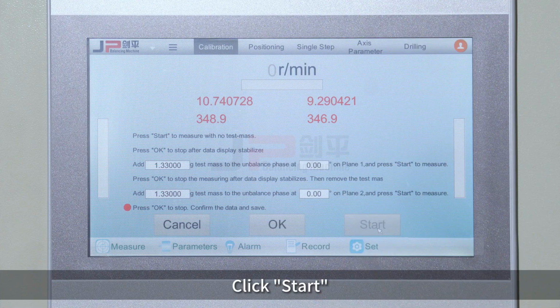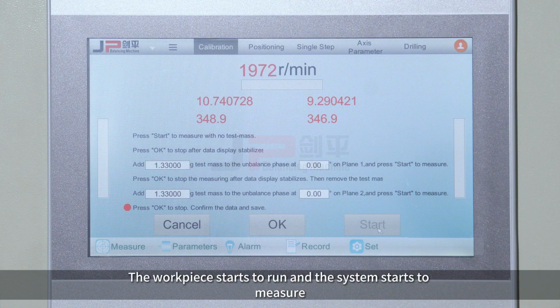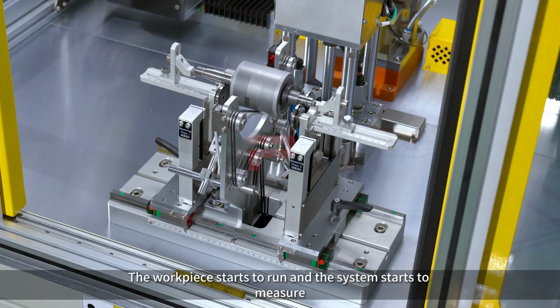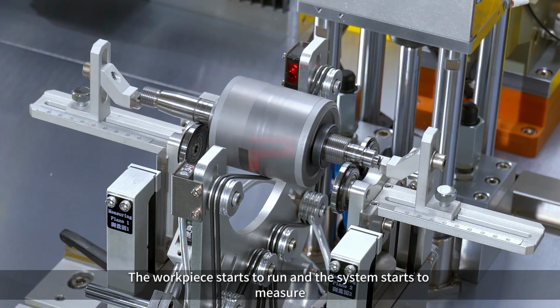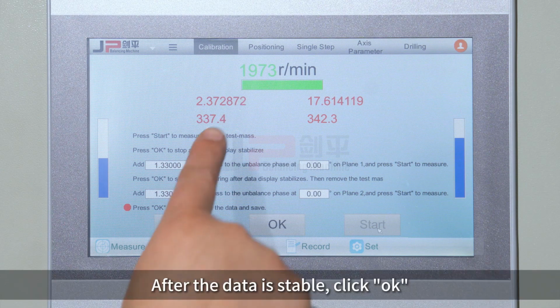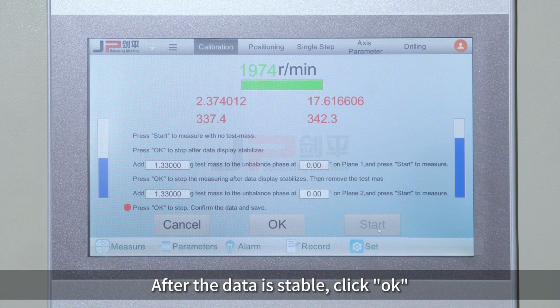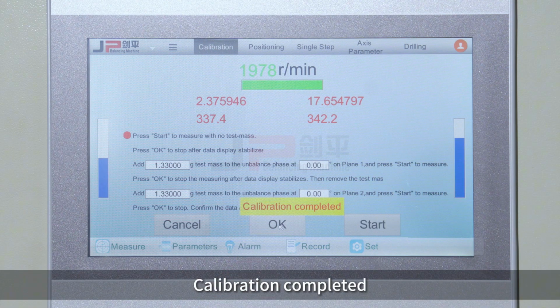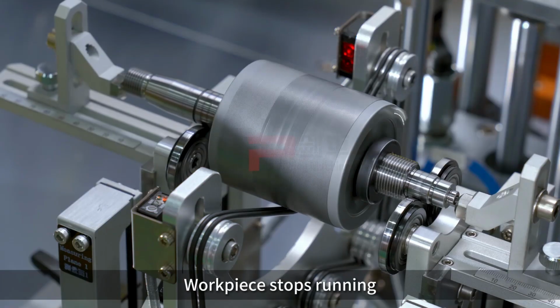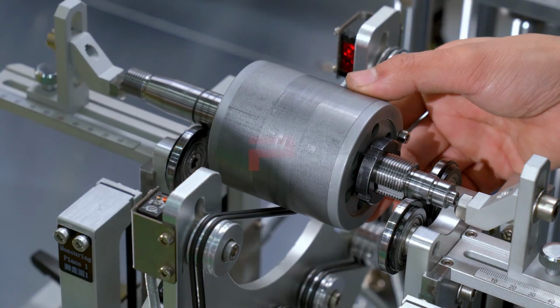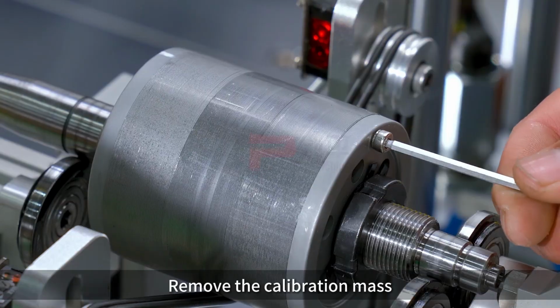Click Start. The workpiece starts to run and the system starts to measure. After the data is stable, click OK. Calibration completed. The workpiece stops running. Remove the calibration mass.